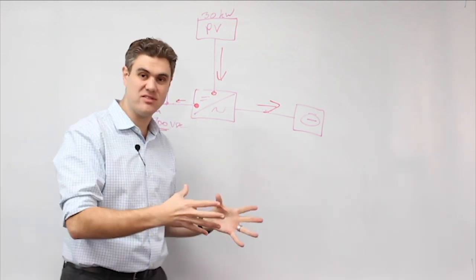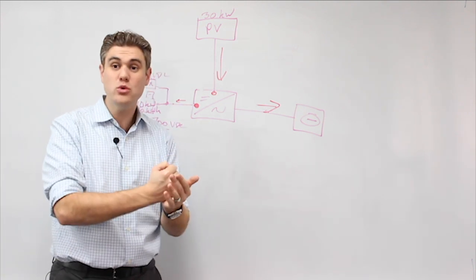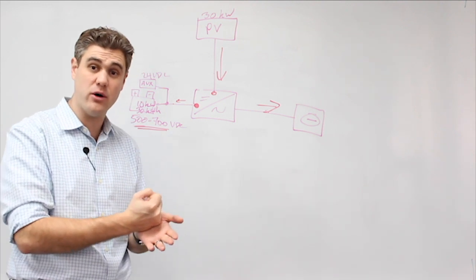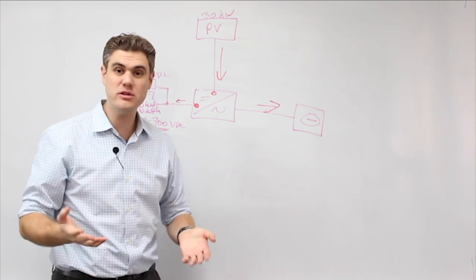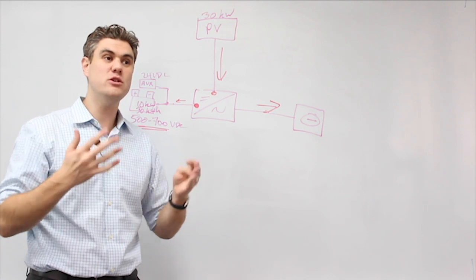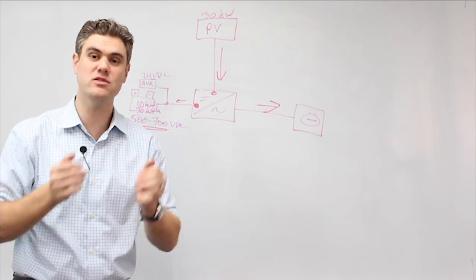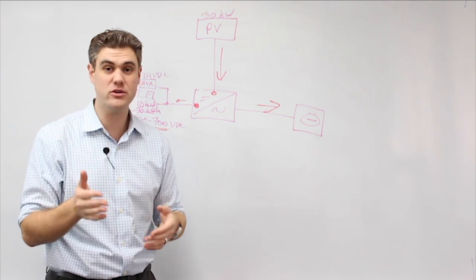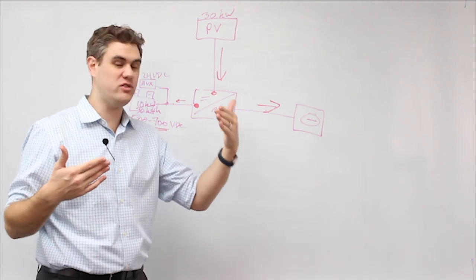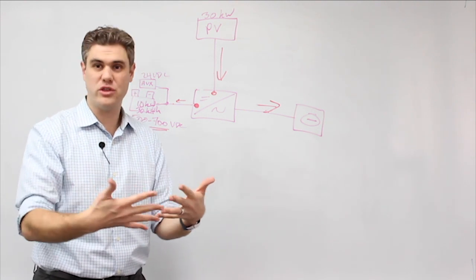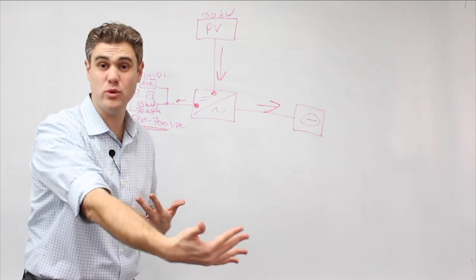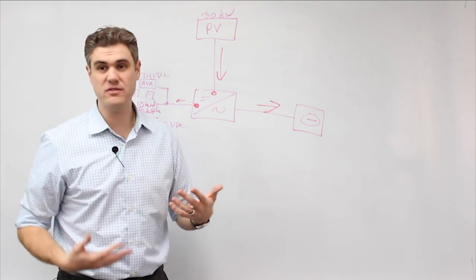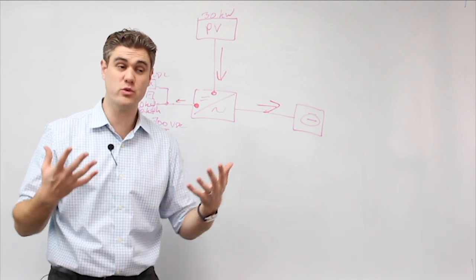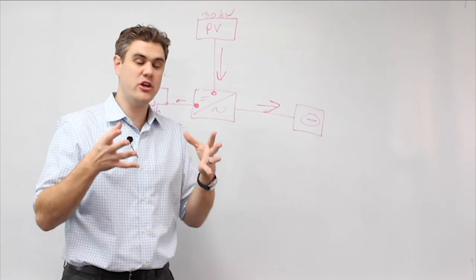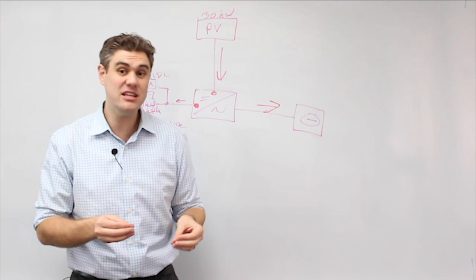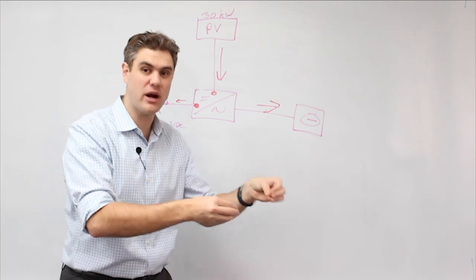And that's something that can be tested for and slapped with a UL verification or certification logo or sticker or stamp. In other words, the utility company can trust a third party to do that work for them. And that's really critical. You never want to be in a situation where it's you versus your regulator, with no check and balance in between. This is why IEEE 1547 and UL 1741 for inverters was so popular and great, because it was something that could be verified in the lab. It did not need to be verified in the field on every single project.